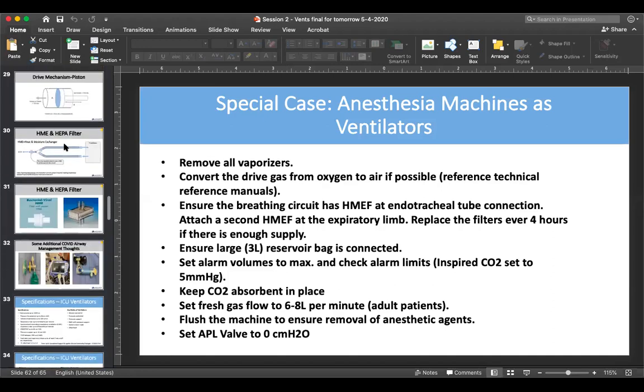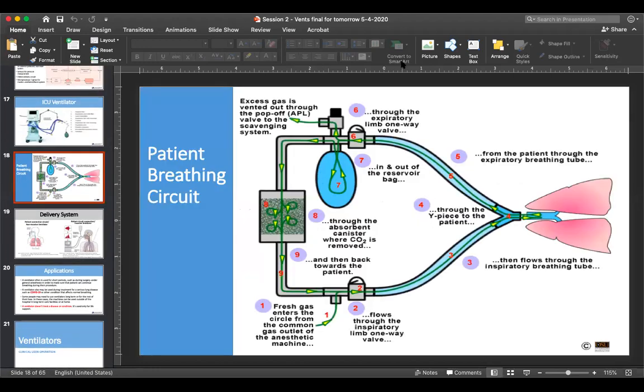So, if I could just quickly show you this picture. If this is the circuit for a COVID-19 patient, you will have an HMEF filter right after the Y-piece on this end. And then you'll have another HMEF filter perhaps before it gets to the expiratory valve. Between those two filters, you should be able to capture all of the viral organisms, the virus and bacteria in the circuit. You will only replace the soda lime as it changes color. And I think that's it.